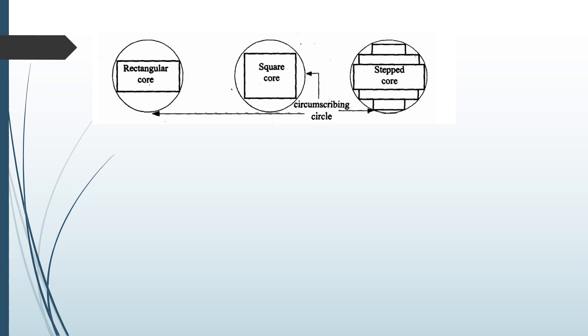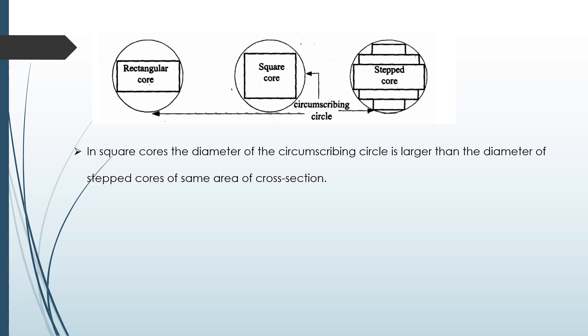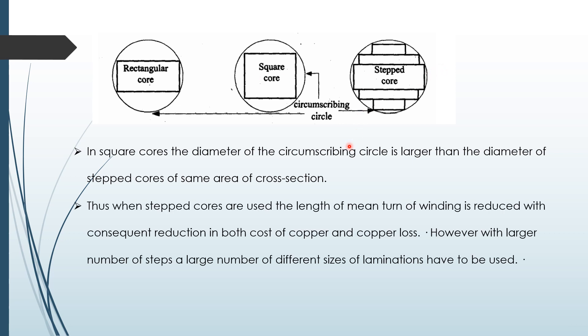In a square core, the diameter of the circumscribing circle is larger than the diameter of a step core of the same area of cross section. Thus, when step cores are used, the length of the mean turn of winding is reduced, with a consequent reduction in both the cost of copper and copper loss.